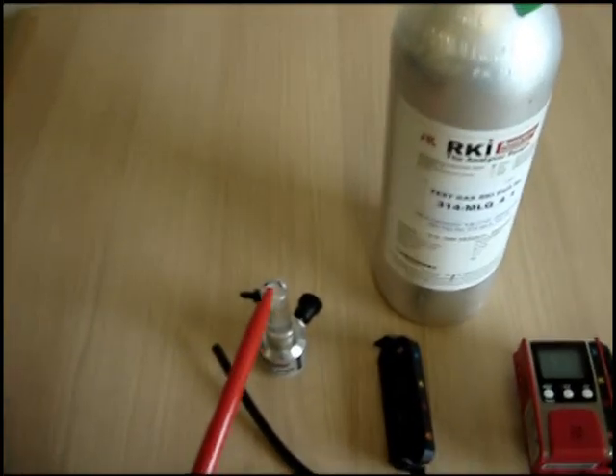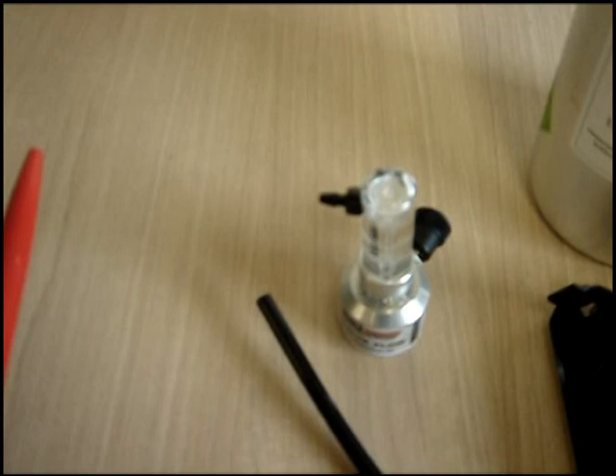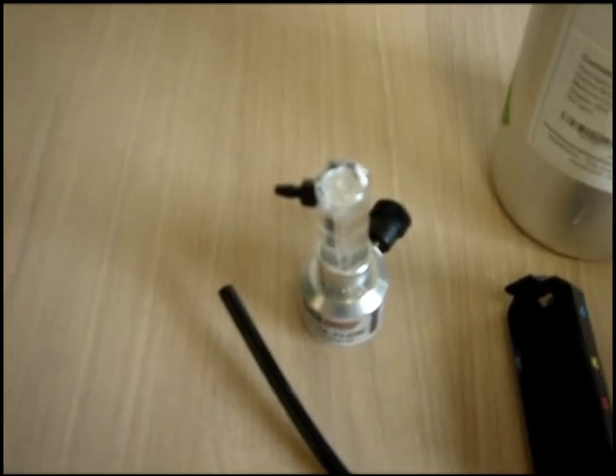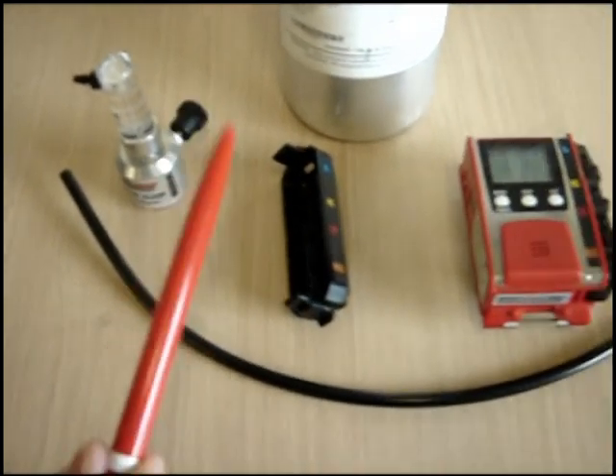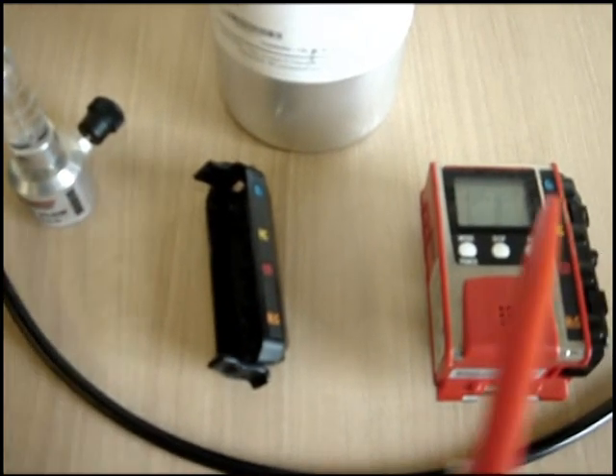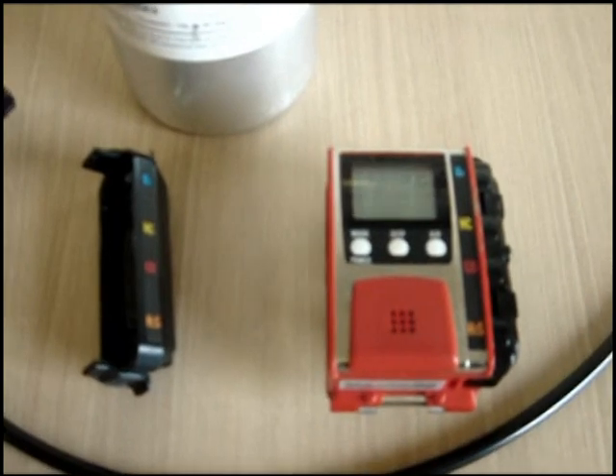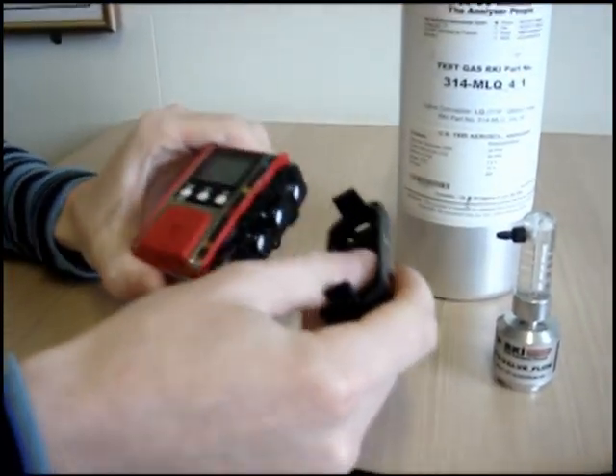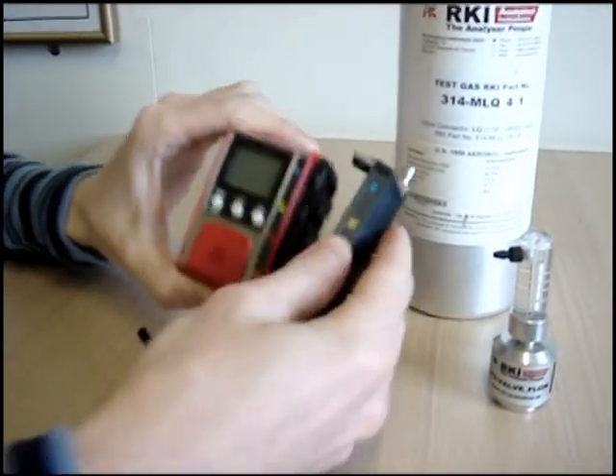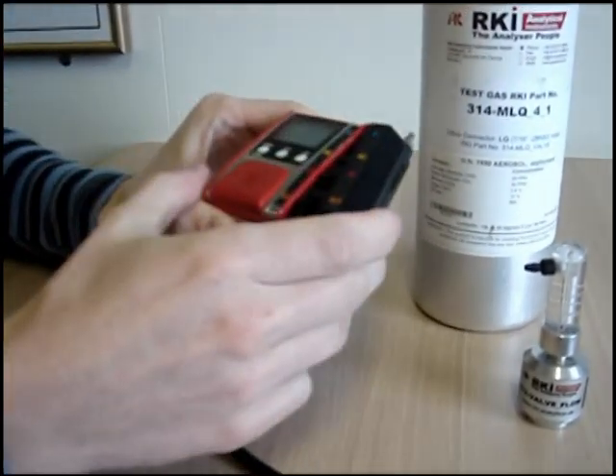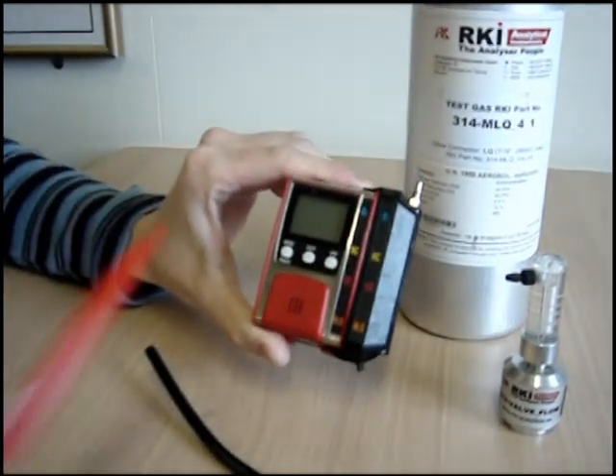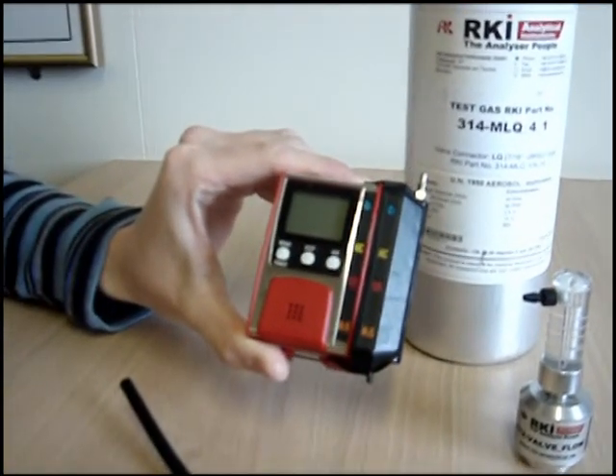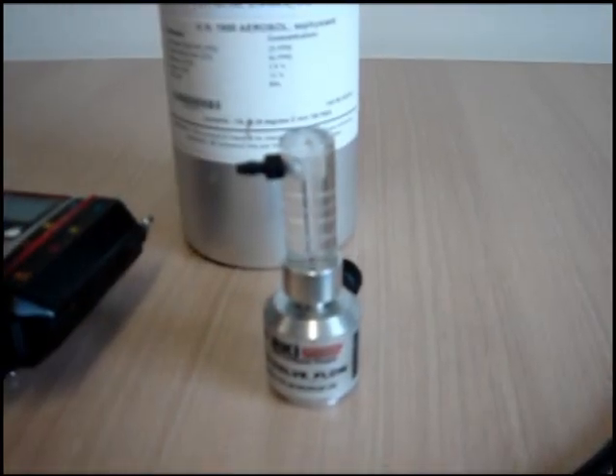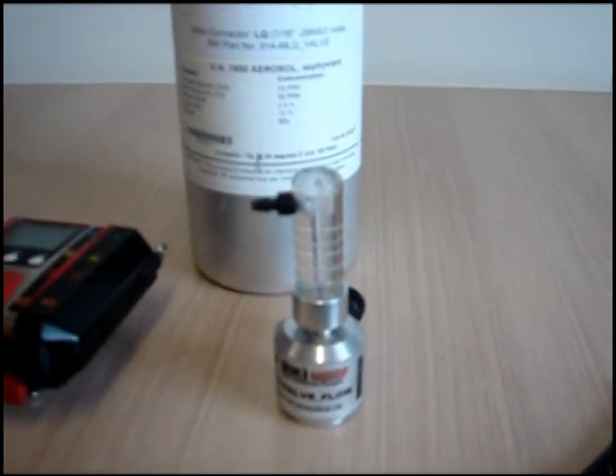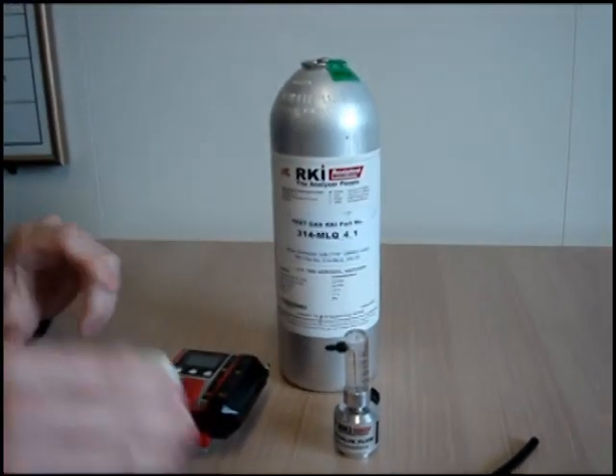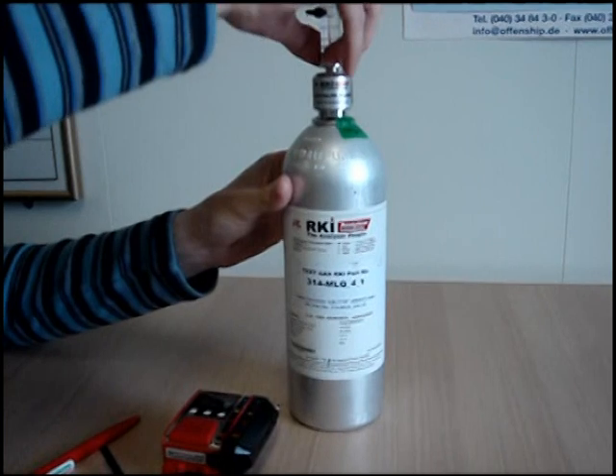The next one is the flow meter, which is used to control the flow. To use as little gas as possible, we will use the portable hose connected to the flow device connected to the gas detector. To connect the flow device to the gas detection equipment, you have to start from the top. Connect it here, and then you push. Now it is connected, and all the gases correspond to each other. The next step is to connect the flow meter to the gas bottle. For this purpose, you remove the gas cap, take the flow meter, and connect it to the bottle.